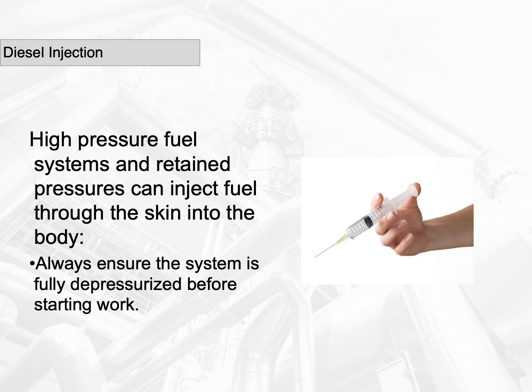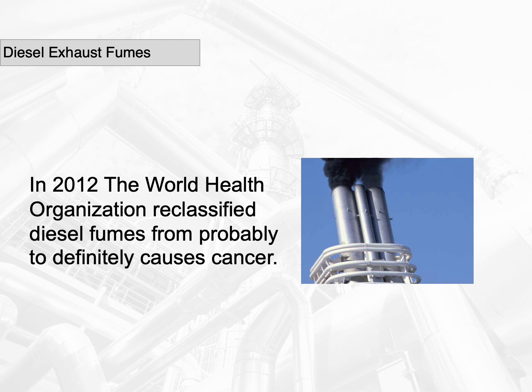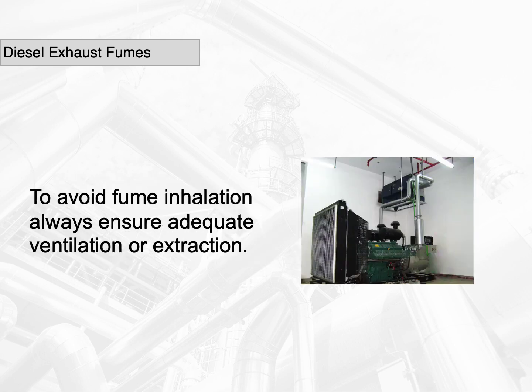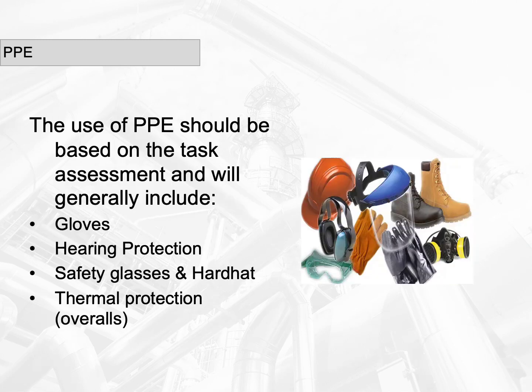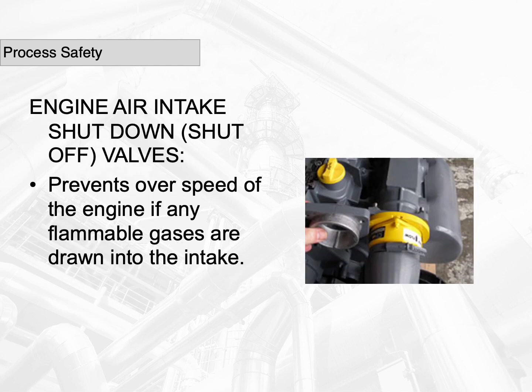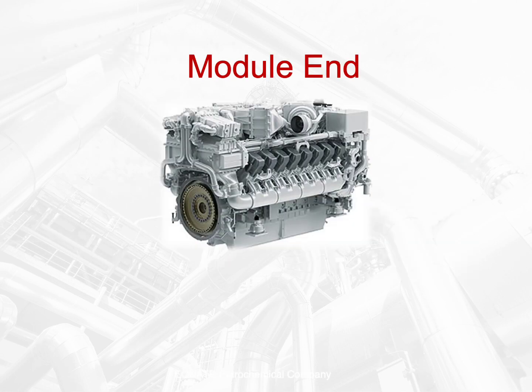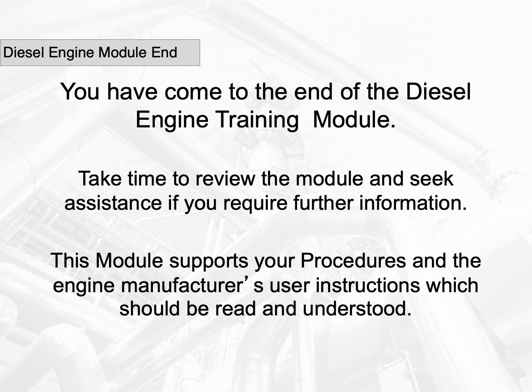High-pressure fuel systems and retained pressures can inject fuel through the skin into the body. Always ensure the system is fully depressurized before starting work. In 2012, the World Health Organization reclassified diesel fumes from probably to definitely causes cancer. To avoid fume inhalation, always ensure adequate ventilation or extraction. The use of PPE should be based on the task assessment and will generally include gloves, hearing protection, safety glasses, and hard hat, and possibly thermal protection, overalls. Engine air intake shutdown valves prevent overspeed of the engine if any flammable gases are drawn into the intake.